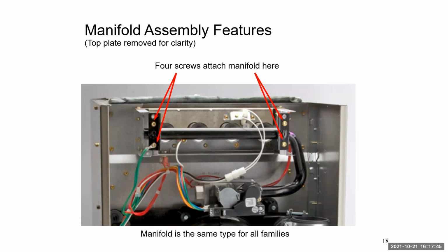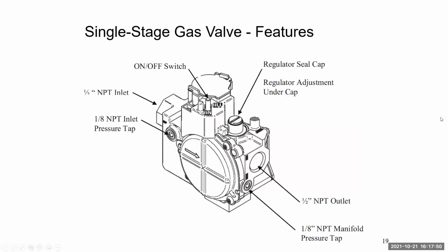Matthew Jorgensen, any issues with propane kits on these burner assemblies? No, as long as they're properly taken care of and serviced every year, so make sure you're scrubbing them, because they do soot up. You will get the propane soot up on them, especially if your gas pressure is off. So make sure that they're taken care of. What about the screws, Matthew?